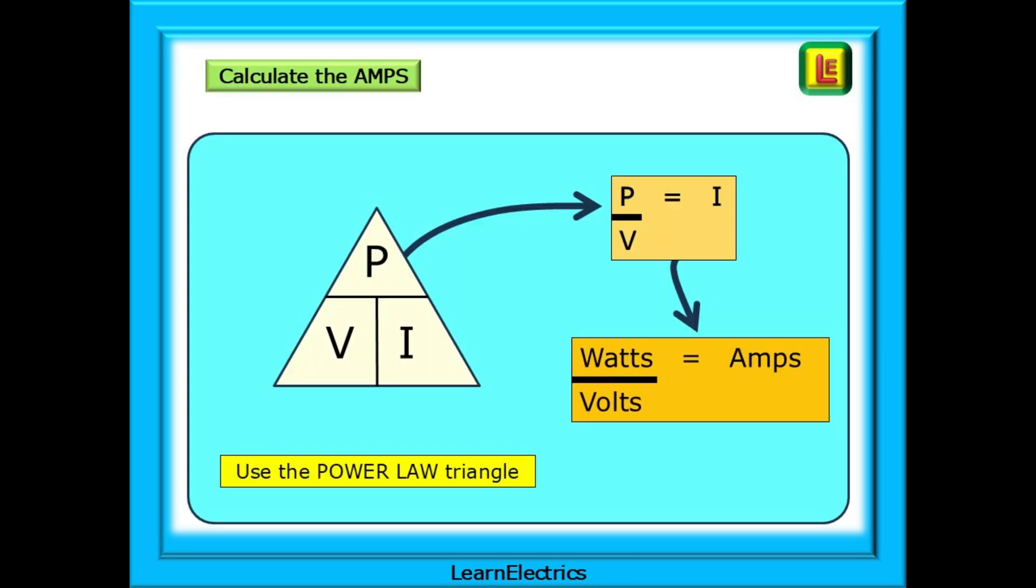Very often, we will know the watts or kilowatts for the load or appliance, but we need the information in amps. For this, we can use the power law triangle as shown here. If we know the power, P, in watts, and we know the voltage, V, of the circuit, then we can easily calculate the amps. P divided by V gives I. Or, some people will say, watts divided by volts will tell us the amps.